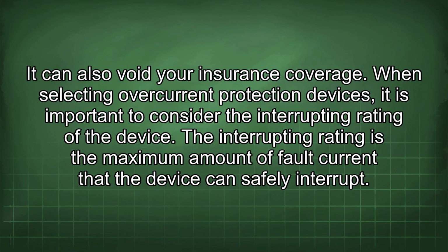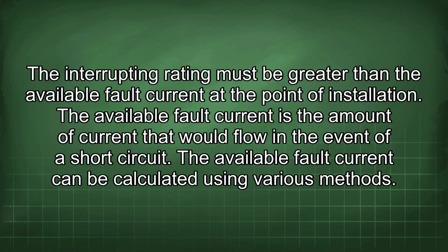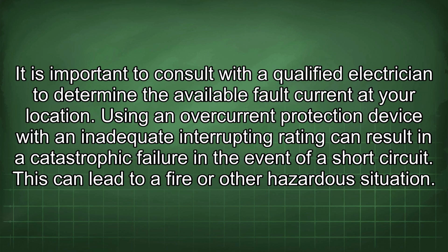When selecting overcurrent protection devices, it is important to consider the interrupting rating of the device. The interrupting rating is the maximum amount of fault current that the device can safely interrupt. The interrupting rating must be greater than the available fault current at the point of installation. The available fault current is the amount of current that would flow in the event of a short circuit. The available fault current can be calculated using various methods. It is important to consult with a qualified electrician to determine the available fault current at your location.